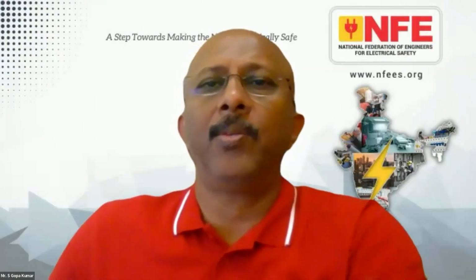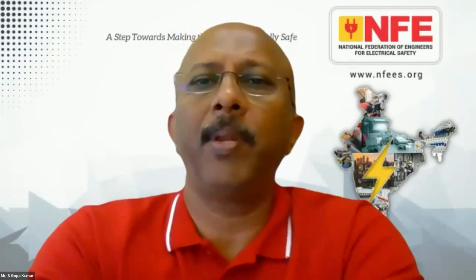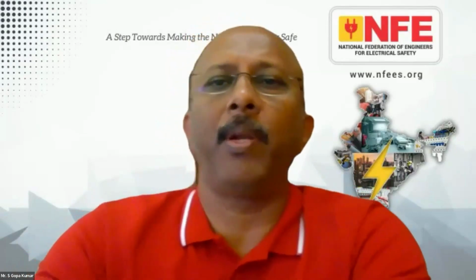Okay, that's great. So we have the next question from Mr. Rajan Menon. Is any sector mandatory to continuously monitor IEEE 519? IEEE 519 is to be monitored continuously, because whatever you do as a test is done for 1 week. If you continuously monitor, you see that the loads are not going to be the same, the loading pattern is not going to be the same, and the dynamics of the upstream grid also change. So it is always better to monitor continuously and know what is happening in your system. If someone comes and monitors IEEE 519 for 1 week and then gives the result, it is not necessary that the same results would come every week. Every week the results can change. For that reason, IEEE 519 needs to be monitored continuously.